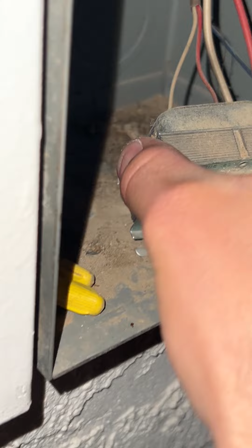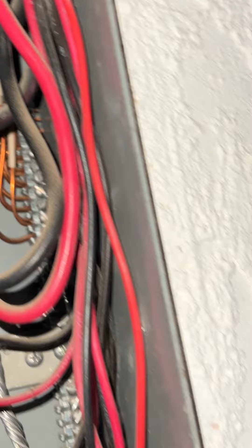Man, the quality of those wires is pretty good for a 40-year-old, 45-year-old home. These breakers aren't too bad. Someone actually didn't do too bad wiring this house up, I gotta say. I'm a little impressed with this panel. So that's your incoming power up there. It's pretty cool. Got some 10 gauge, some 14-3, 14-2, standard stuff. Back then you could tell they used red as hot, so these red wires coming in here.